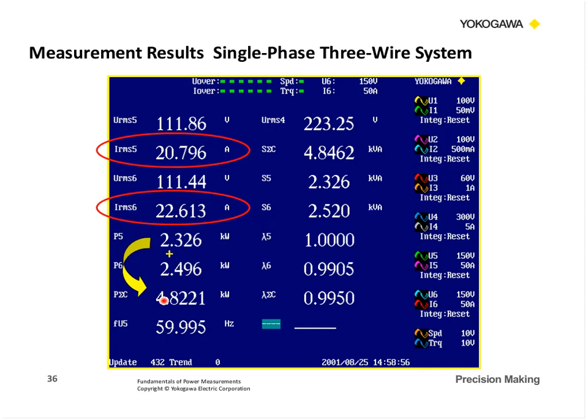And then our total power was down here. We had a power factor. Look at this. This is interesting. I had a power factor on one line at unity, so that's all resistive. But we had a power factor on the other line at 0.99. So there is a difference in the load internally on this device.